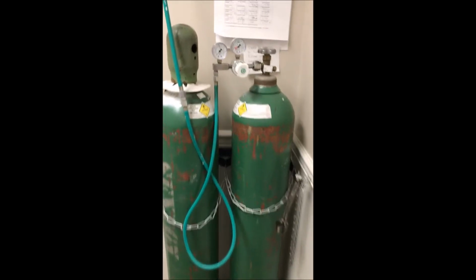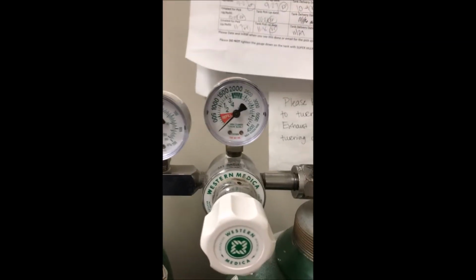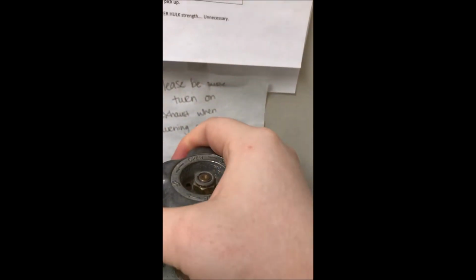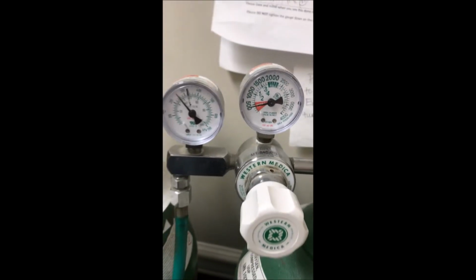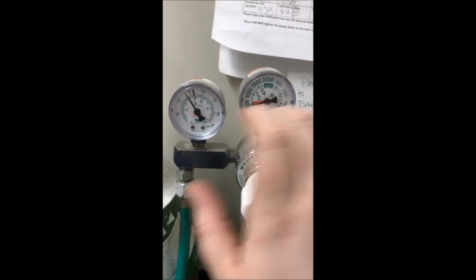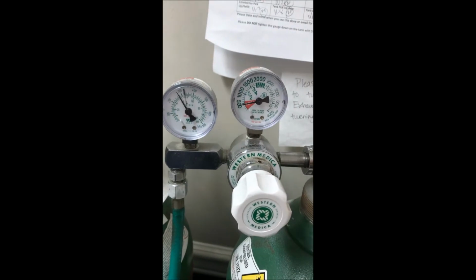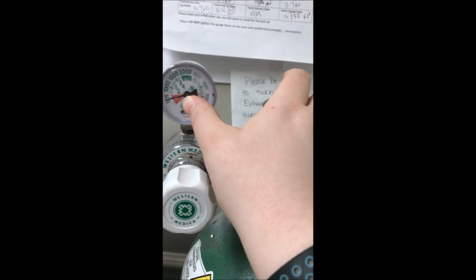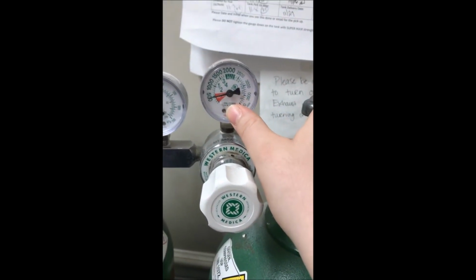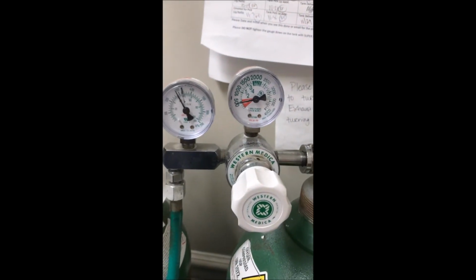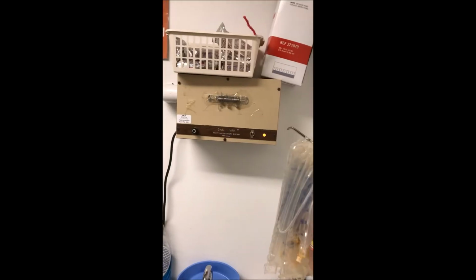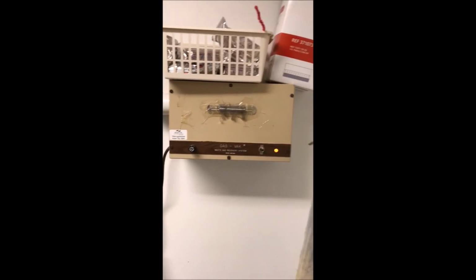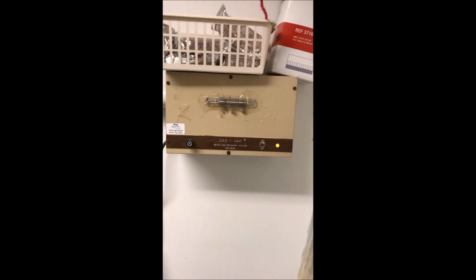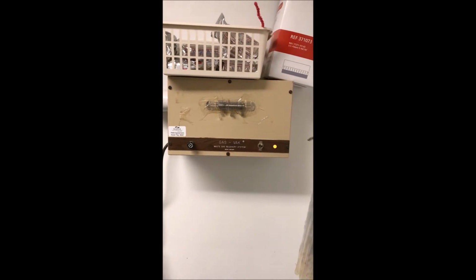At our hospital, we also have a mark for when we turn on our oxygen. We know not to fill it past our line pressure gauge. We have a maximum of what we like to have full. As you can tell, we're getting dangerously low, and we'll need to swap this out on Monday before we start doing any surgeries. This is our gas vac. It actually is our exhaust. We always make sure we turn that on after we turn on our oxygen tank so that we can make sure that everything is evacuated properly.